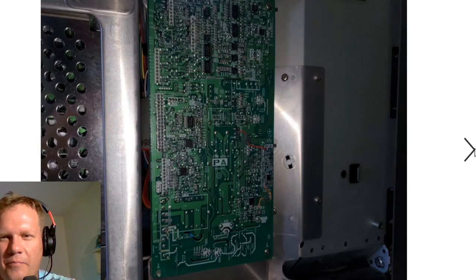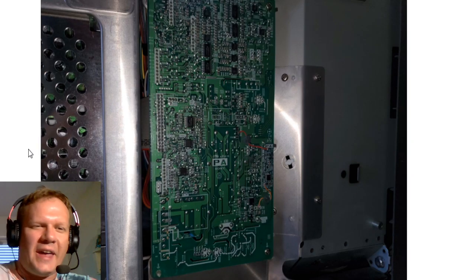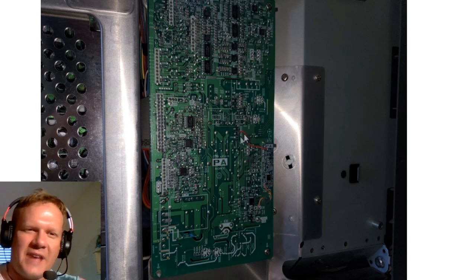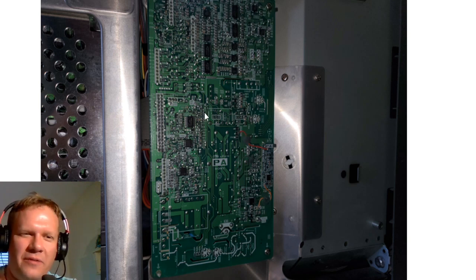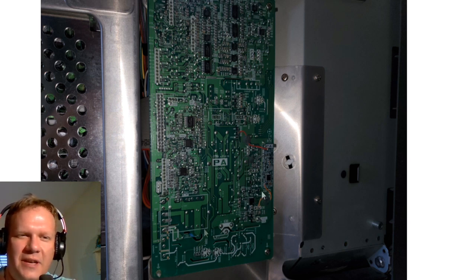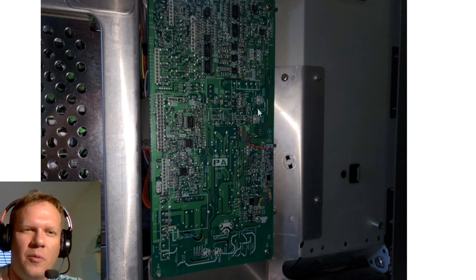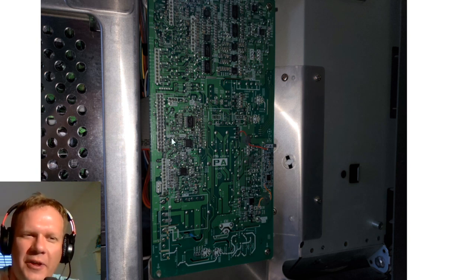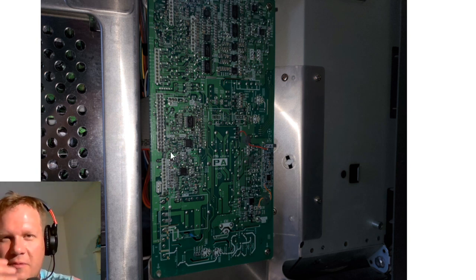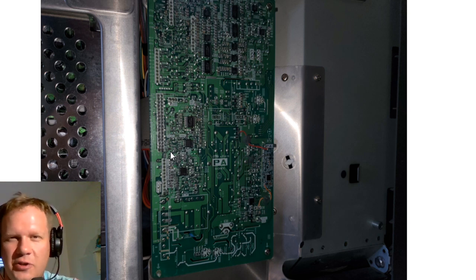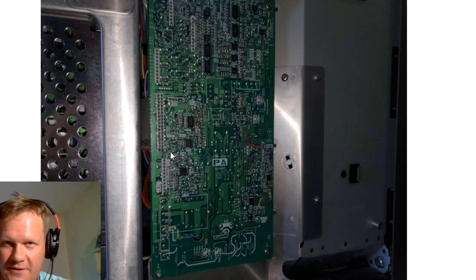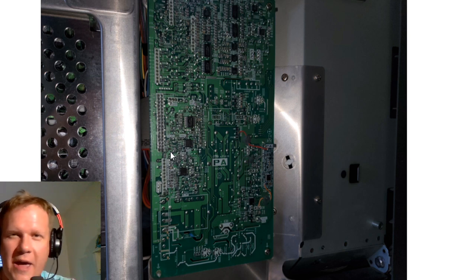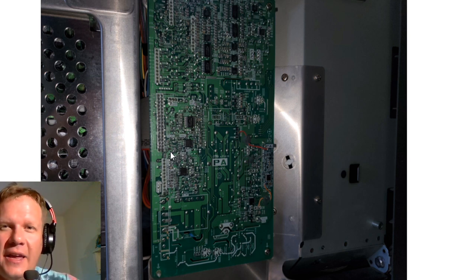So that's what we think happened. We think this had the worst thing happen. It was 25,000 hours, and they'd been using the brightness and contrast to keep up with the picture and keep it viewable, which was burning down the tube life. This is normally a tube that burns at a lower brightness than other tubes, and it's got the power in it to physically push the beam way beyond the capability of the tube itself to withstand the pressure.